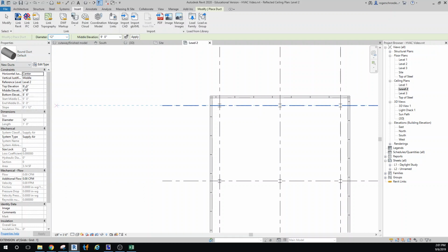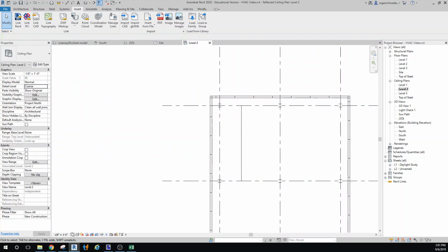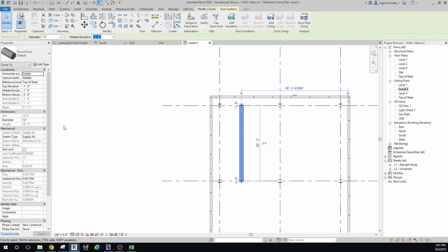Right now I'm thinking about locating it so it doesn't hit the beams, so we want to pick some kind of relationship to our elements. We can go top of steel, and we know we want to be 1 foot below the top of steel because that's the depth of our steel element. So I'll go top elevation 0, and we'll draw in a piece of ductwork. Then I'll set our view to fine so we can see it has a depth to it—you'll notice the one I set for 12 inches, and you can adjust that diameter.